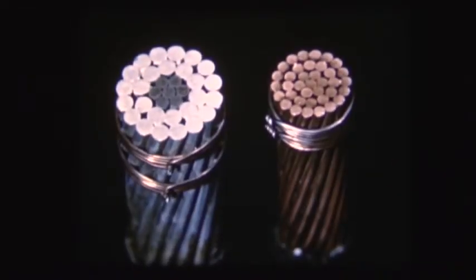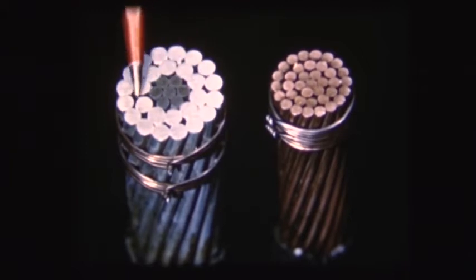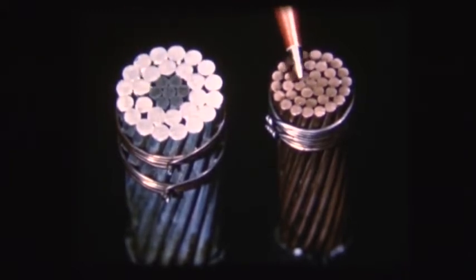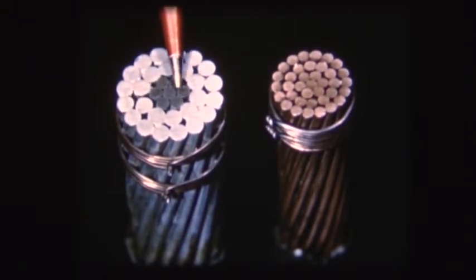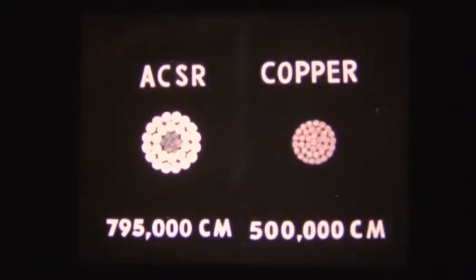Because of aluminum's lower conductivity, somewhat larger sizes must be used than if copper were chosen. And because of its lower tensile strength, a steel core is used in situations where reinforcement would not be necessary for copper. A typical conductor used on Columbia River System 230,000 volt lines is ACSR, Aluminum Conductor Steel Reinforced, with 795,000 circular mils of aluminum. This material has a copper equivalent of 500,000 circular mils. That is, its carrying capacity is equal to an unreinforced stranded copper conductor of 500,000 circular mils.